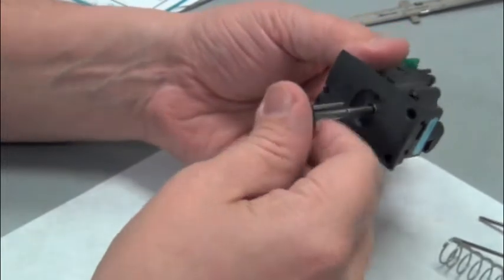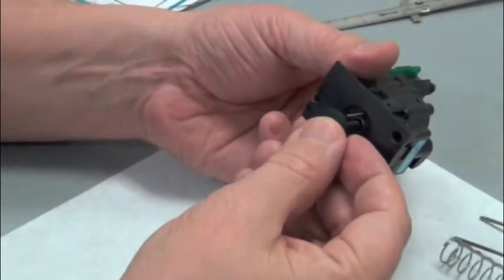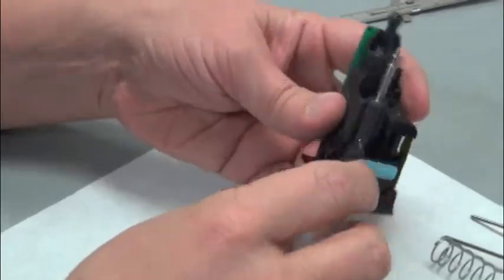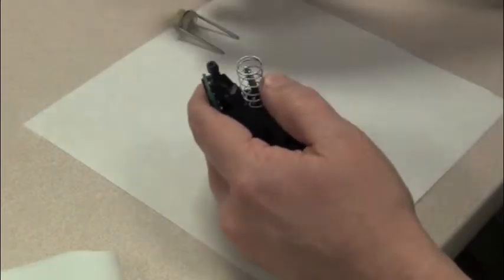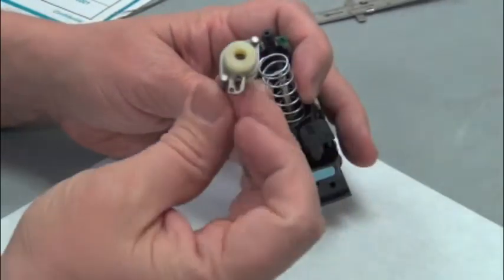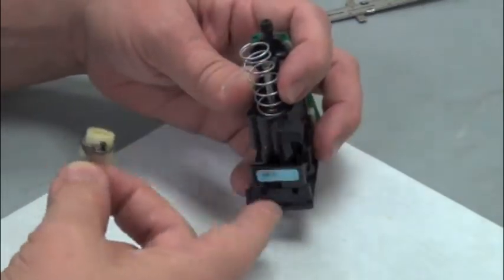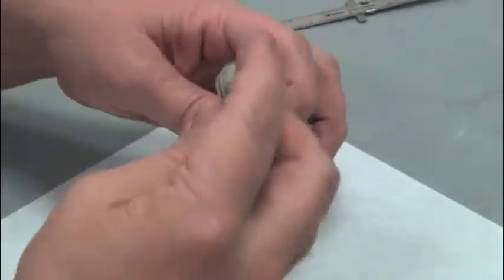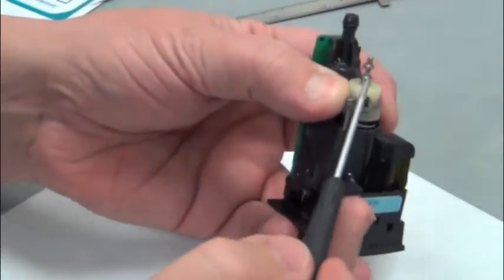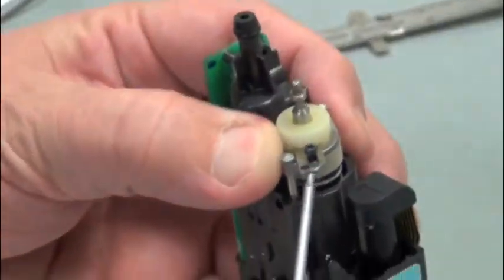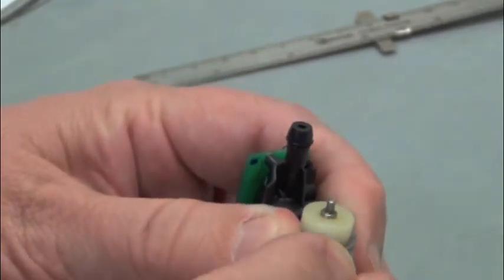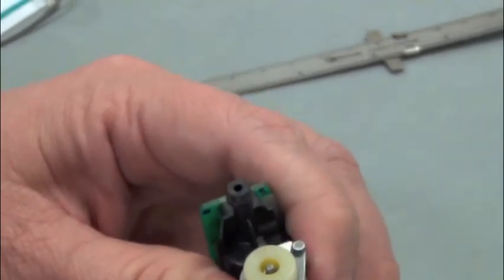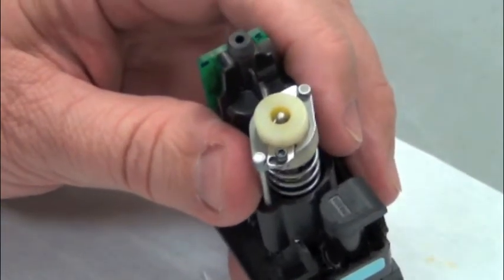Place the spindle in the housing with the theta home sensor keyed in the hole. Take the spring and put it on top. Take the spindle cap. We want to make sure that the screw is facing forward or facing the theta motor with the label on the spindle. Slide it all the way down past this groove so you can see that groove, and we want to slide this into that groove. So we slowly let it slide up as we put a little pressure on the spindle. And because we never removed this screw, we can then go right back in and tighten that screw down.